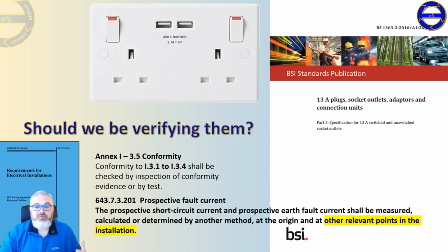Let's get into it a bit more, because there's a statement in the wiring regulations in section 643 7 3.201 that got me really thinking. It says the prospective short circuit current and prospective earth fault current should be measured, calculated or determined by another method at the origin and at other relevant points in the installation. It was the 'other relevant points' that got me thinking, why can't I do that at the USB? Should I be verifying any short circuit, or proving at least that short circuit? Should I be looking at the voltage output, the power output, and seeing whether it protects itself? Because in that standard there's lots of criteria, henceforth section 3.1, 3.4.